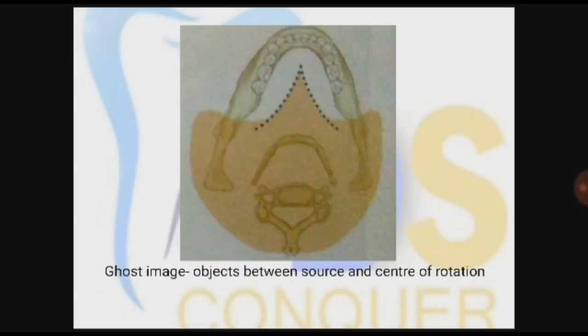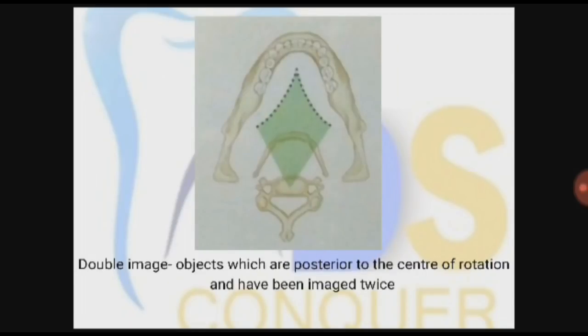The ghost image is formed of the objects which are between source and center of rotation. The source, that is the tube head, is never going to the endmost anterior part, so the anterior part is spared. The double image is formed of objects which are posterior to the center of rotation and have been imaged twice. It comes in this diamond-shaped area. Only these objects will be imaged double and are posterior to the center of rotation.